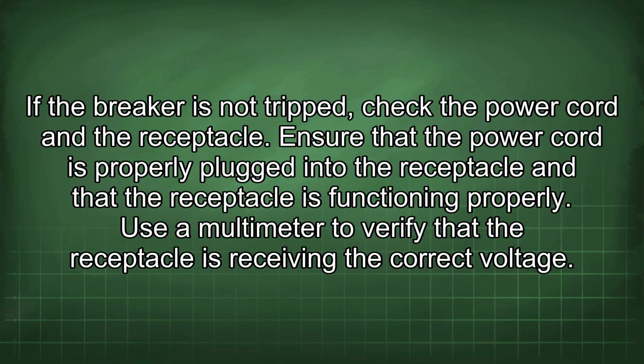wiring. If the breaker is not tripped, check the power cord and the receptacle. Ensure that the power cord is properly plugged into the receptacle and that the receptacle is functioning properly. Use a multimeter to verify that the receptacle is receiving the correct voltage.